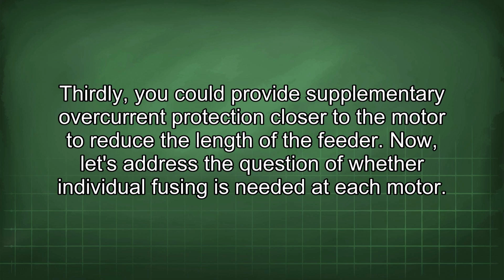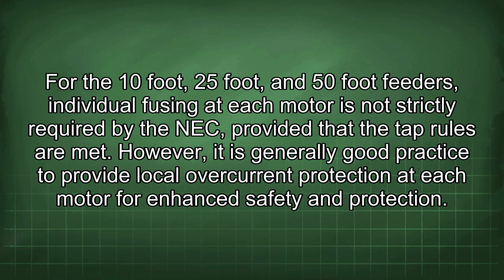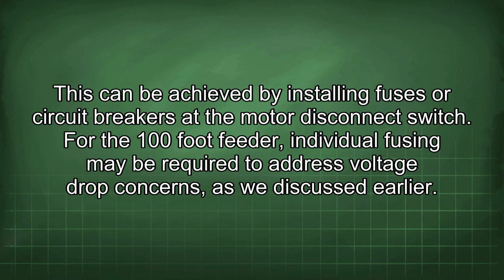Now, let's address the question of whether individual fusing is needed at each motor. For the 10-foot, 25-foot, and 50-foot feeders, individual fusing at each motor is not strictly required by the NEC, provided that the tap rules are met. However, it is generally good practice to provide local overcurrent protection at each motor for enhanced safety and protection. This can be achieved by installing fuses or circuit breakers at the motor disconnect switch.